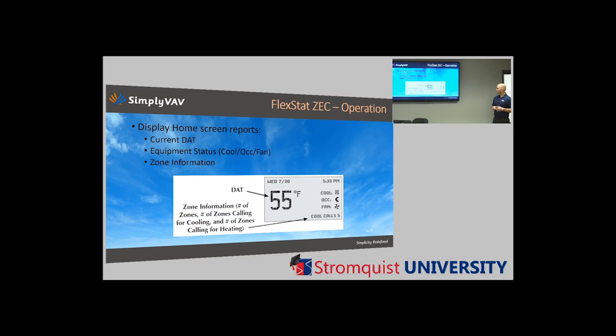When it's operating, the display will show you current discharge air temperature. It will also give you quick status of what the equipment's doing, if cooling's active, if you're occupied or unoccupied, or if the fan is running. The fan can run continuously while occupied, or it can cycle as a configurable property. And then it will tell you how many cool calls or heating calls are active or how many zones are connected. So quick troubleshooting, make sure all the devices you think are communicating are actually seen on the system and are reporting their demand.